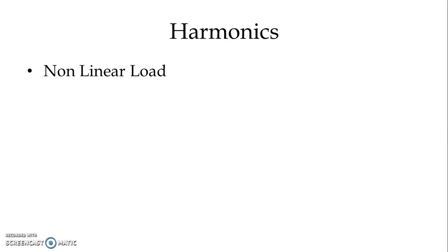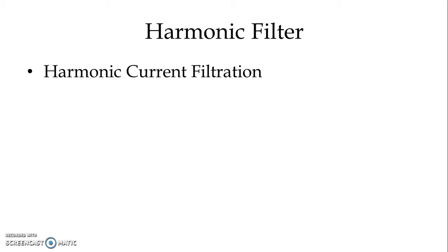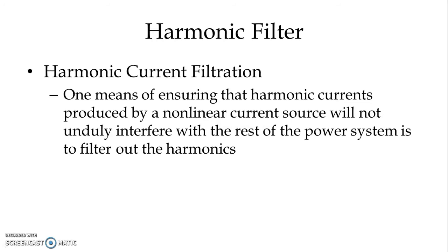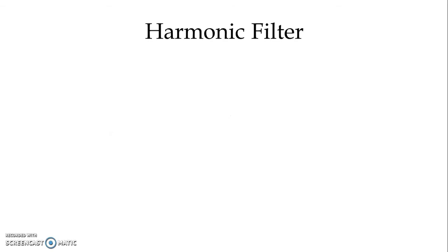Because of nonlinear loads, harmonic current is generated and this harmonic current will propagate towards the source. It will have harmful effects on the power system as a whole, and we need to filter out this harmonic current. Harmonic current filtration is one means of ensuring that harmonic currents produced by a nonlinear current source will not unduly interfere with the rest of the power system.